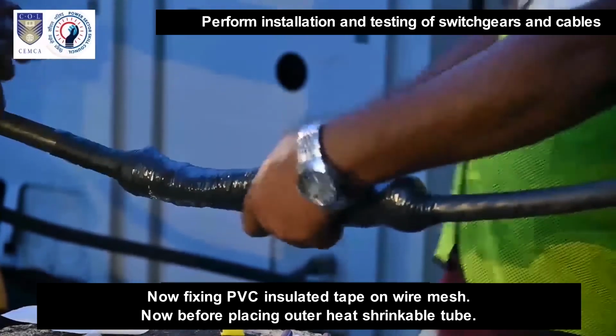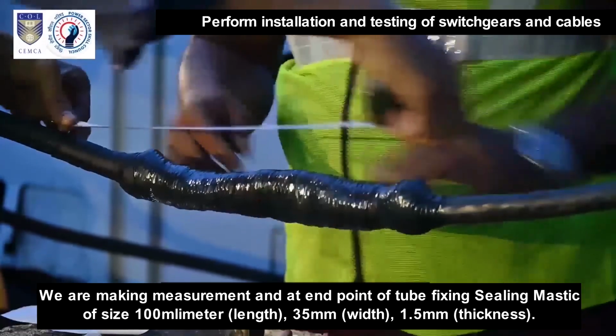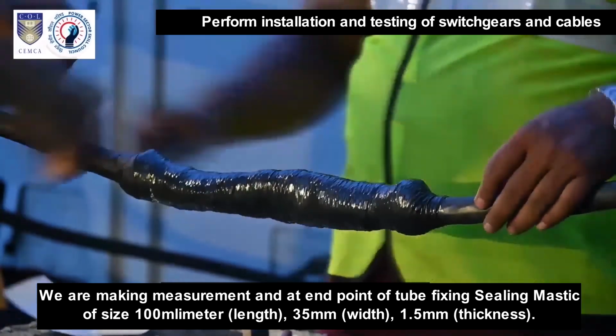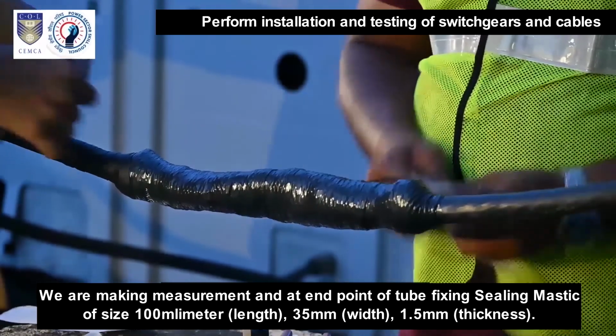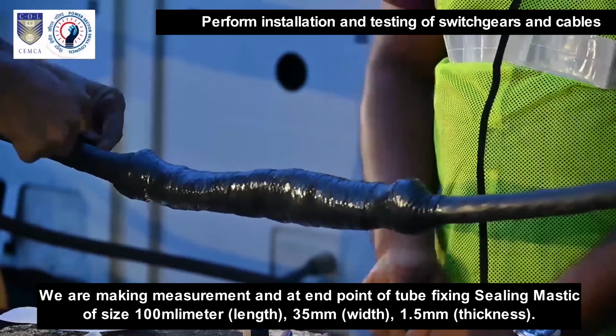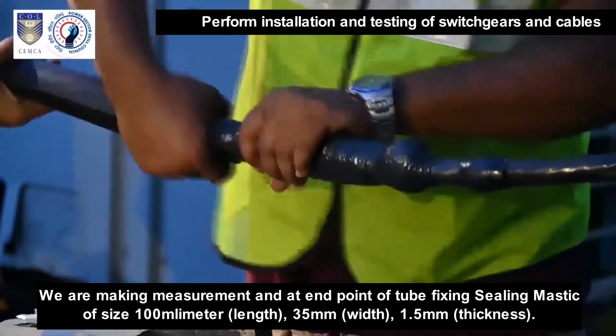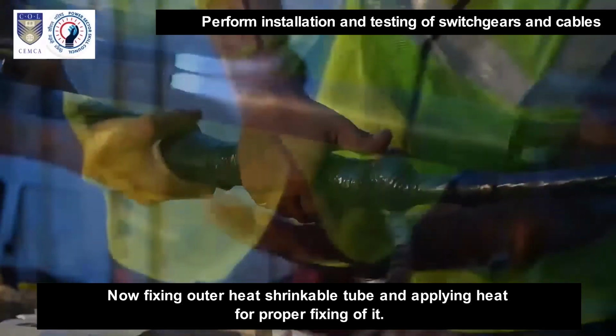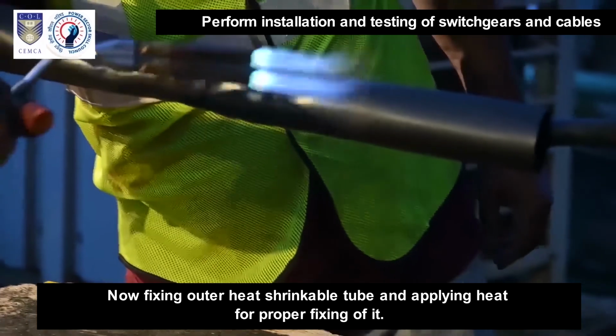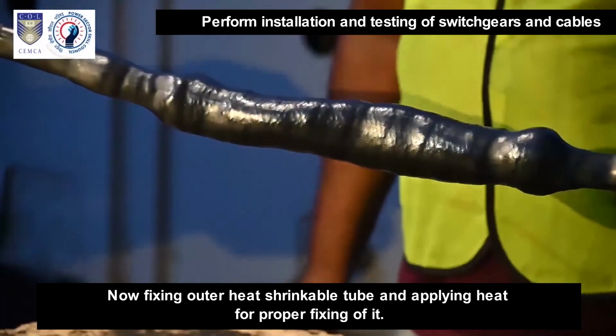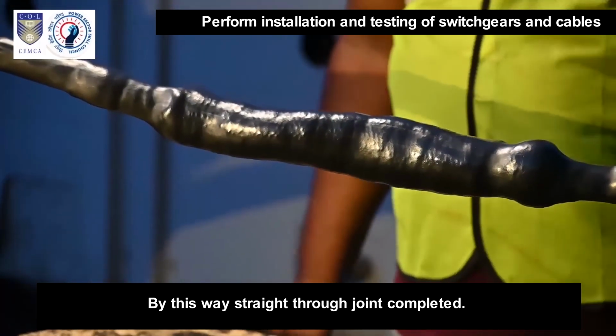Now before placing the outer heat shrinkable tube, we are making a measurement at the end point of the tube, fixing sealing mastic of size 100 mm length, 35 mm width, 1.5 mm thickness. Now fixing the outer heat shrinkable tube and applying heat for proper fixing of it. In this way, the straight through joint is completed.